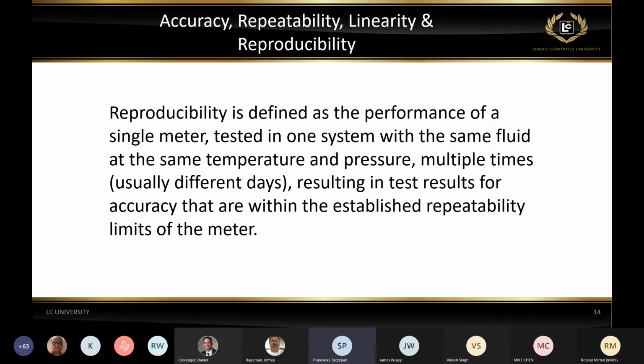Now, reproducibility is probably a term that's not used very commonly, but it's also important. It is defined as the performance of a meter that is tested on one system, on the same liquid, same pressure, same temperature, but possibly on different days. That's reproducibility. Can we reproduce the same result from day to day? Not from run to run, which is more of a repeatability, but from day to day. Generally, if the meter is repeatable, it will be reproducible. That's a general statement on that.